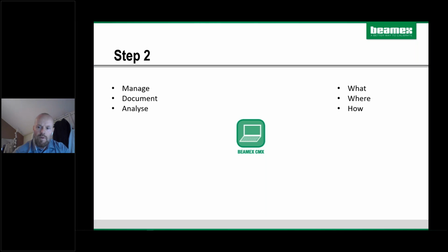The beauty of a system like this is when you have seamless communication between the calibrators and the software. So when you as a technician have a job to do, you just select the work order or the instrument that is due for calibration, and you download everything to the calibrator. You take the calibrator with you out in the field and do your job, then come back and upload everything back to the system, and everything is done.